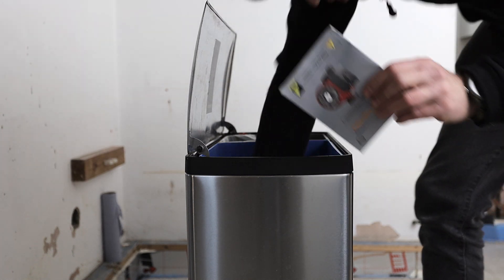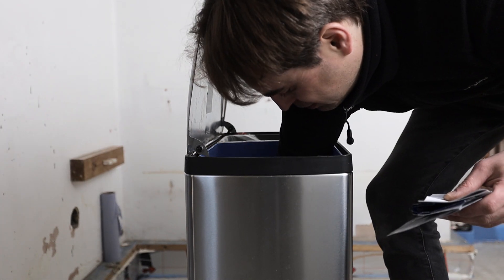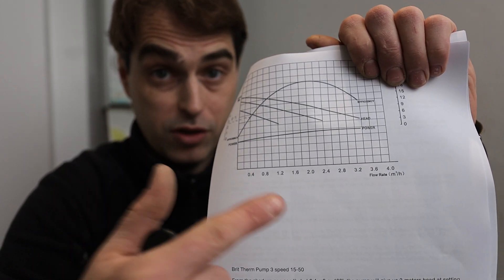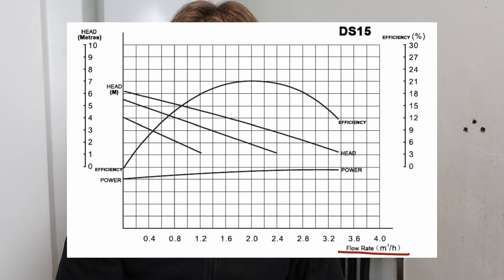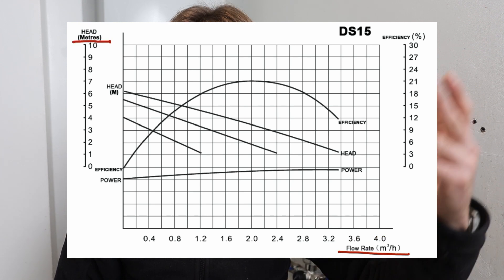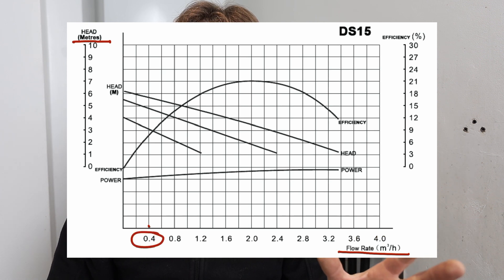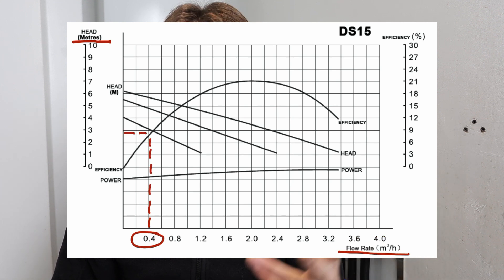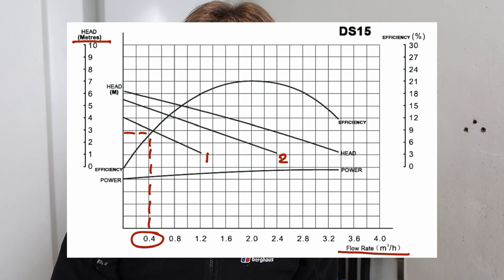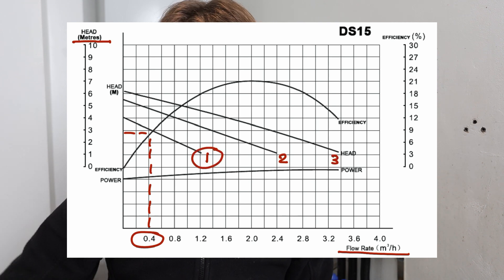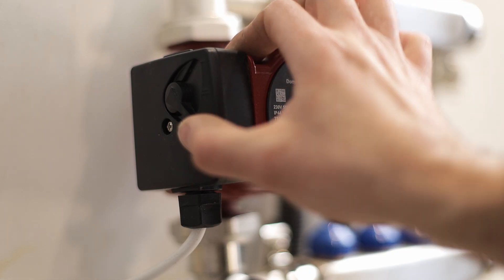Now find that manual you binned earlier, dig it out and find the pump chart. On the horizontal axis you get your flow in liters per hour or cubic meters per hour; on the vertical axis you get the available pump head. At 0.4 cubic meters per hour we're getting around 2.5–2.7 meters of pump head available, and we only need 1.2 meters. Looking at the chart, setting number one provides more than enough head, so there's no need to run the pump higher than setting one. Drop it from 3 to 1.